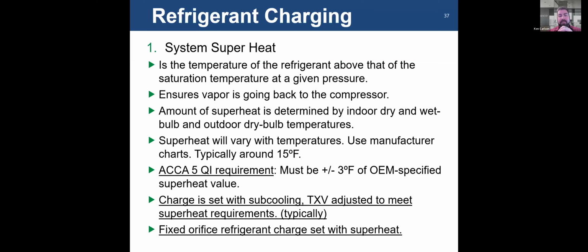That's a good standard. Even if ACCA 5 doesn't say that, that's a good metric to use. And you want to get as tight as possible. There's variations in how you read your gauge. There's variations in the gauge itself. There's a level of tolerance of accuracy, even in your equipment.